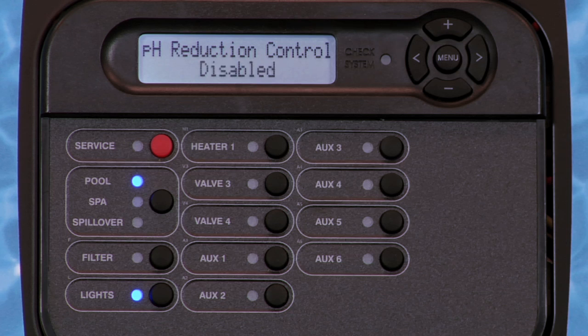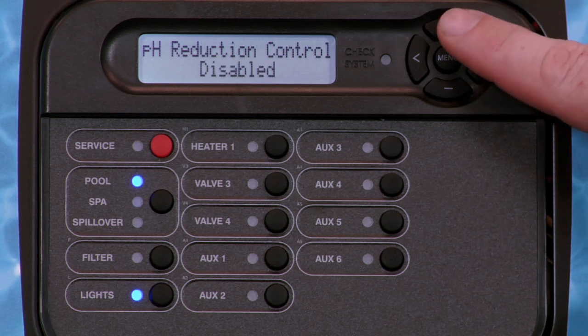pH reduction control disabled is the next display you will see. When Sense and Dispense is used with the ProLogic, you have the option to reduce the water's pH by adding either CO2 or muriatic acid to the water. By pressing the plus key to enable pH reduction control, you allow the ProLogic to turn on an output to reduce the pH, such as an acid feed pump or a solenoid valve for a CO2 tank.